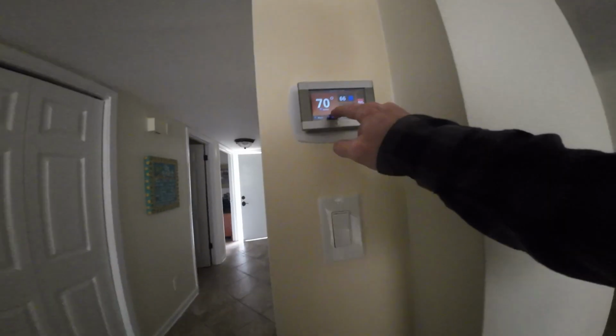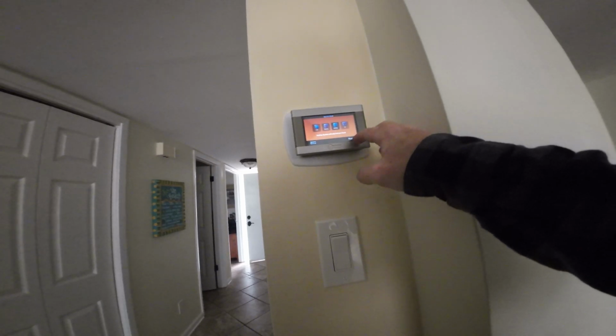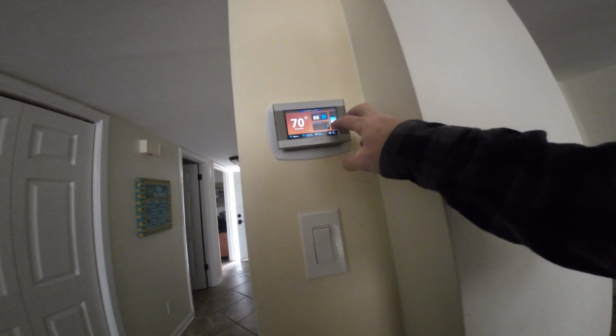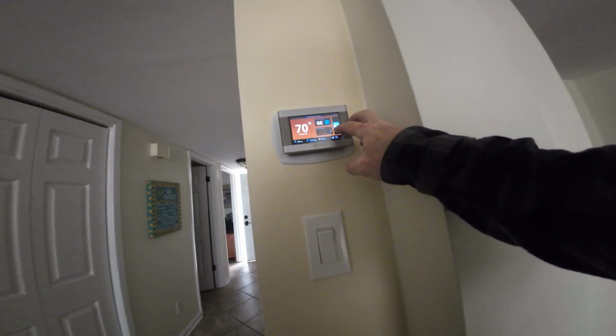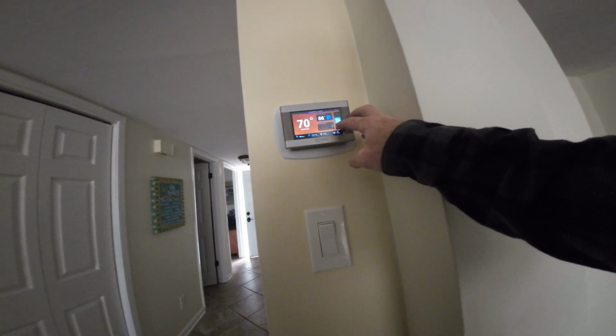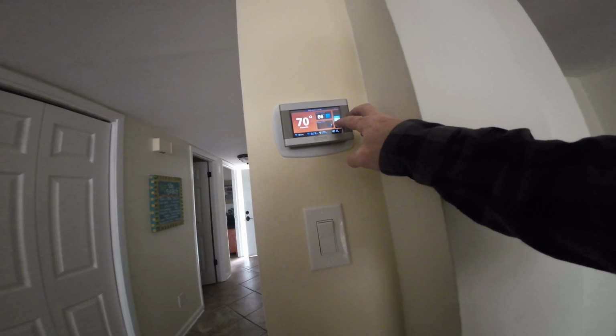Alright. So it looks like it kicked the heat pump off and turned the emergency heat strips on. We're getting 101 on the heat strips only. They're working though. Alright, I'm gonna go kick it in cool mode. We're gonna test the temp split in cool mode. We're gonna go to cooling. Got like 64. I'm pretty sure it ain't gonna cool that quick.